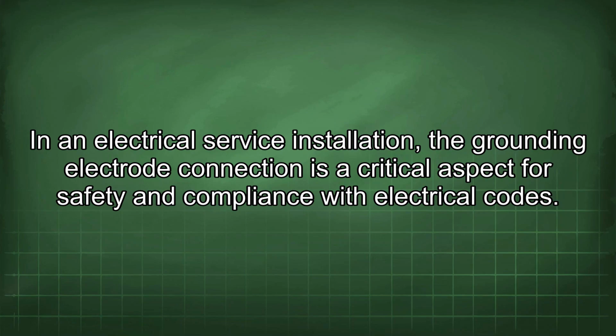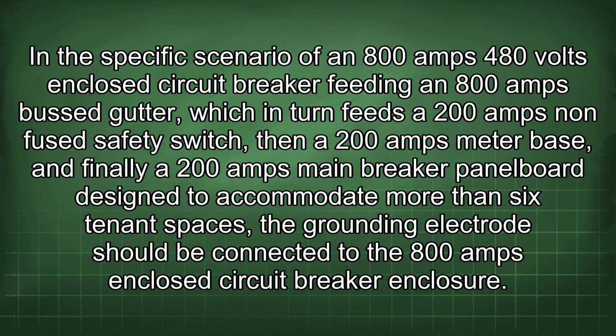In an electrical service installation, the grounding electrode connection is a critical aspect for safety and compliance with electrical codes. In the specific scenario of an 800 amps 480 volts enclosed circuit breaker feeding an 800 amps bus gutter, which in turn feeds a 200 amps non-fused safety switch, then a 200 amps meter base, and finally a 200 amps main breaker panel board designed to accommodate more than 6 tenant spaces, the grounding electrode should be connected to the 800 amps enclosed circuit breaker enclosure.